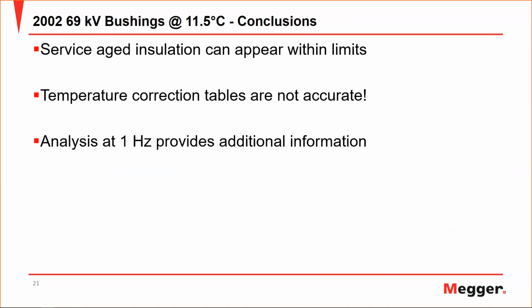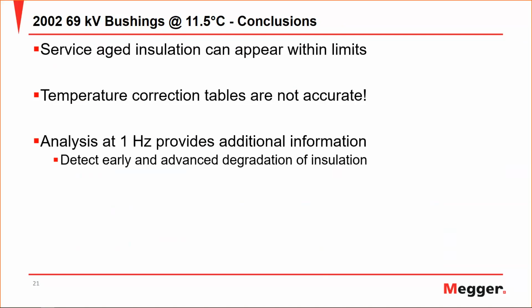Finally, the analysis at 1 Hertz provides additional information, and this is additional information using the same power factor test set that you are using to do the 10 kV line frequency result. And when you do the testing at 1 Hertz, you can detect early and advanced degradation of insulation, which you can then use to improve your maintenance strategy.